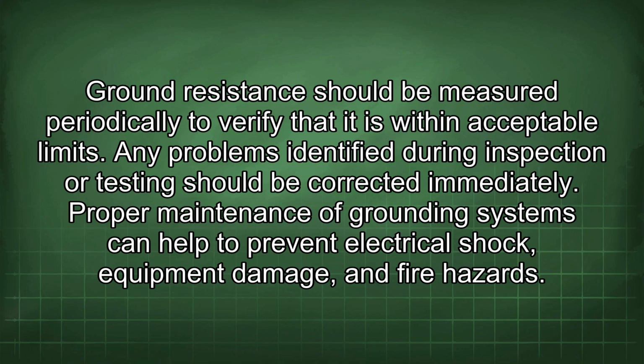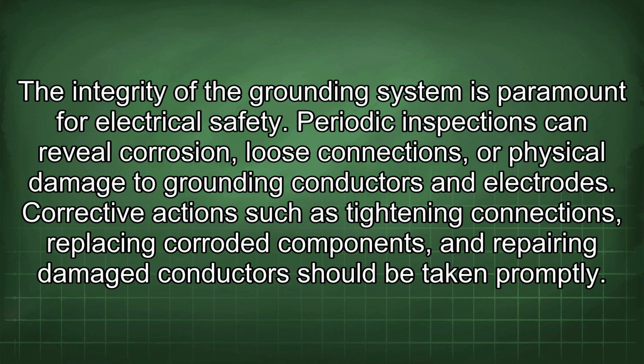Proper maintenance of grounding systems can help to prevent electrical shock, equipment damage, and fire hazards. The integrity of the grounding system is paramount for electrical safety. Periodic inspections can reveal corrosion, loose connections, or physical damage to grounding conductors and electrodes. Corrective actions such as tightening connections, replacing corroded components, and repairing damaged conductors should be taken promptly.